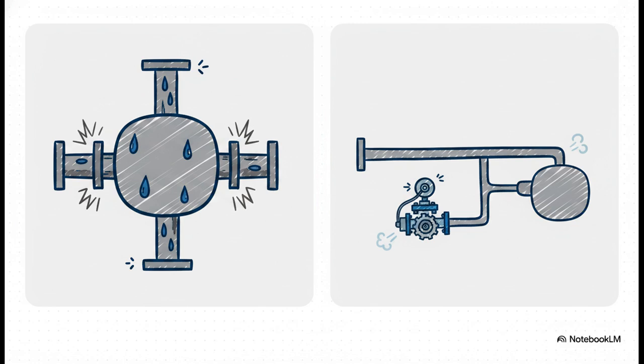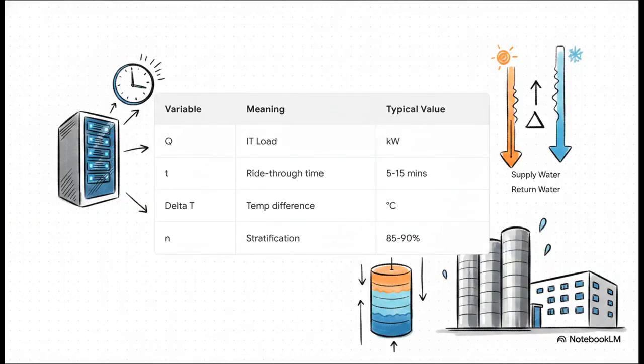On the flip side, the 2-port or bypass method sits alongside the main pipe. Normally, water just bypasses the tank entirely, which means zero pressure loss and super high operational efficiency. But when a blackout hits, you suddenly have to rely on a highly complex automated sequence of motorized valves to instantly redirect the water through the tank to maintain that thermal stratification we talked about. So it's a classic engineering trade-off, right? Simplicity versus efficiency.